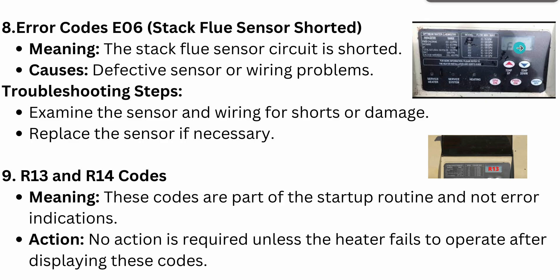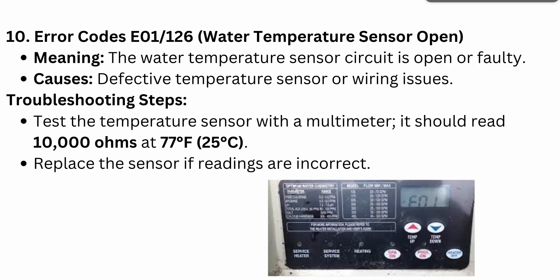Error codes E01 and 126 indicate water temperature sensor open, meaning the water temperature sensing circuit is open or faulty. Causes include a defective temperature sensor or wiring issues. To troubleshoot, test the temperature sensor with a multimeter — it should read 10,000 ohms at 77°F (25°C). Replace the sensor if the readings are incorrect.